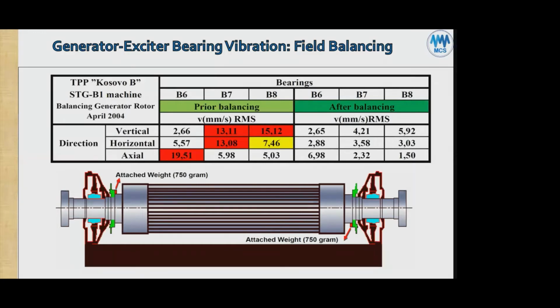However, the rotor is not connected to the grid because they're doing what's called maintenance work on it. So they have obviously disconnected it electrically and isolated it completely so they can add the weights and do the balancing safely. Okay. And you can see where the balance plane is on the green part, which would probably be the fan holder. Maybe it's the balance plane.